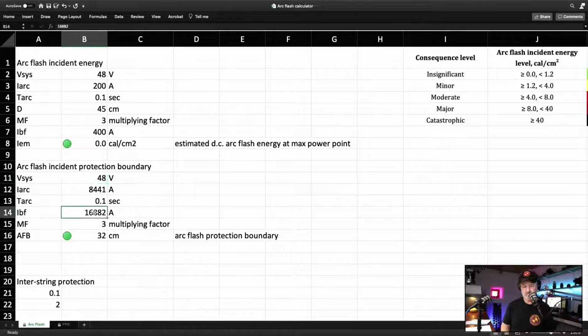Okay, so we actually have a lot less current to deal with, and now we're very safe because of that interstring overcurrent protection. So even though we're working on the main bus bar, which might be as thick as your arm, dropping a spanner across at this point will cause the interstring overcurrent protection fuses or devices to trip and massively limit the current. So there you go. That's how you can design a system to be safe and also to work safely while you're assembling that system.